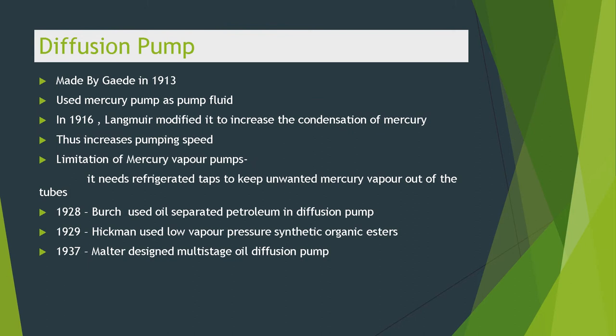Today's topic is the diffusion pump. It was made by Gaede in 1913, who used mercury as the pump fluid. In 1916, Langmuir modified it to increase the condensation of mercury, thus increasing the pumping speed. The limitation of mercury vapor pumps is that they need refrigerated traps to keep unwanted mercury vapor out of the tube.